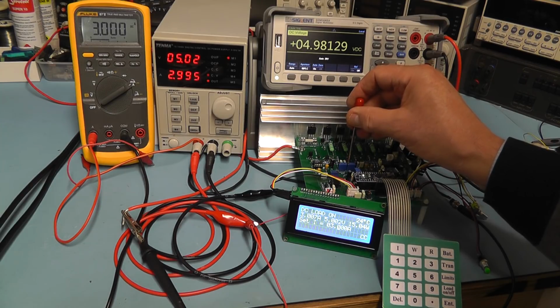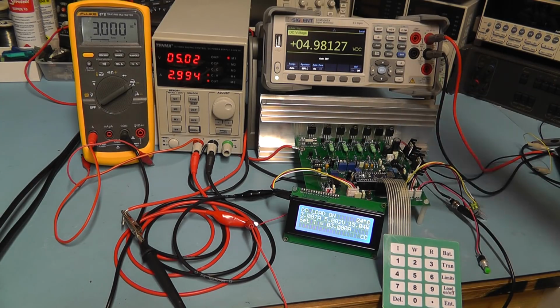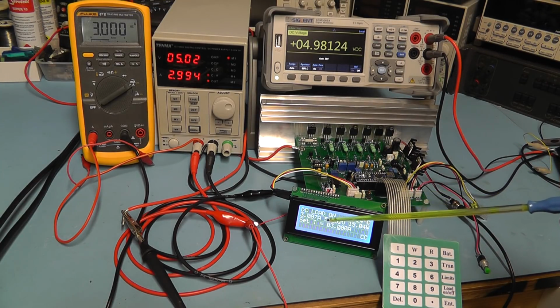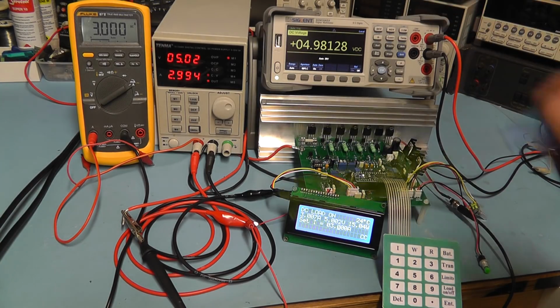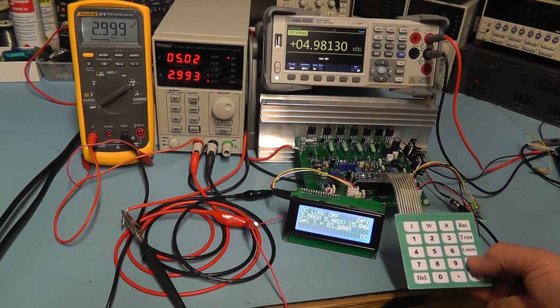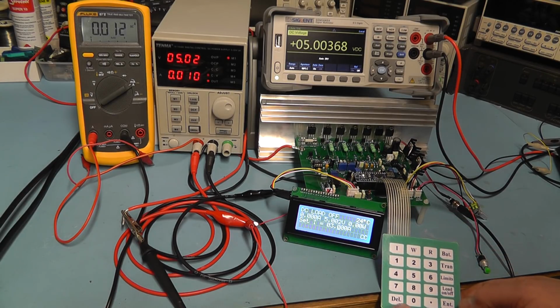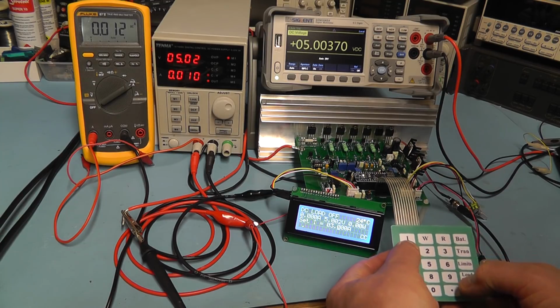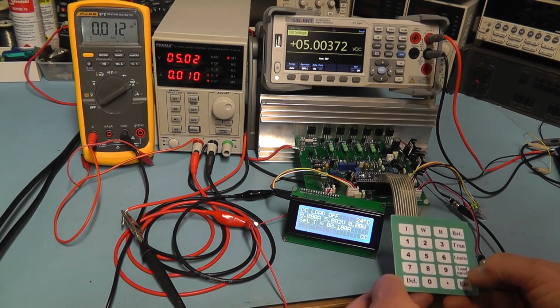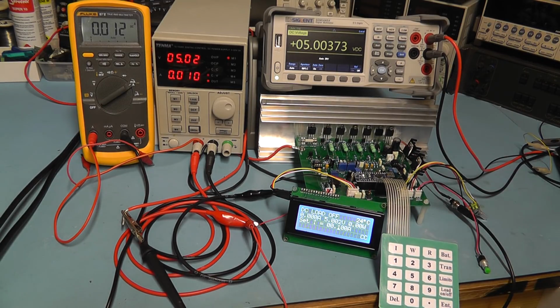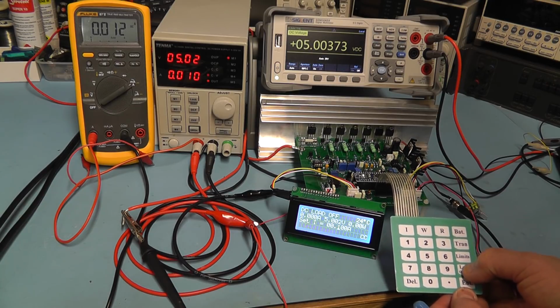until we get 3 amps on the Fluke. Just about there. So we're showing 3 amps there on the Fluke. It's actually showing 3.007 amps on the DC load, but maybe that's within the tolerance. We'll rely on the Fluke for the moment. And the next thing we're going to do is switch the load off. We're now going to set the current to 0.1 of an amp, that's 100 milliamps. And this time when we switch the load on, I'm going to adjust the current null preset till we get the correct reading of 100 milliamps, and that preset is RV3.